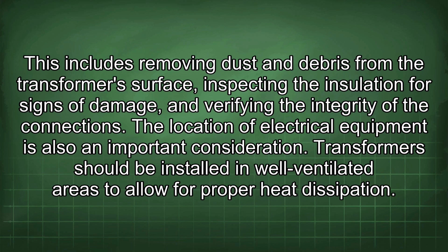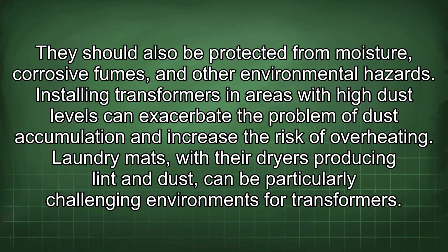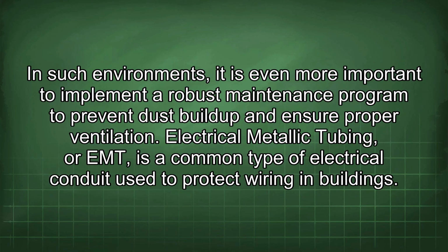Transformers should be installed in well-ventilated areas to allow for proper heat dissipation. They should also be protected from moisture, corrosive fumes, and other environmental hazards. Installing transformers in areas with high dust levels can exacerbate the problem of dust accumulation and increase the risk of overheating. Laundromats, with their dryers producing lint and dust, can be particularly challenging environments for transformers. In such environments, it is even more important to implement a robust maintenance program to prevent dust buildup and ensure proper ventilation.